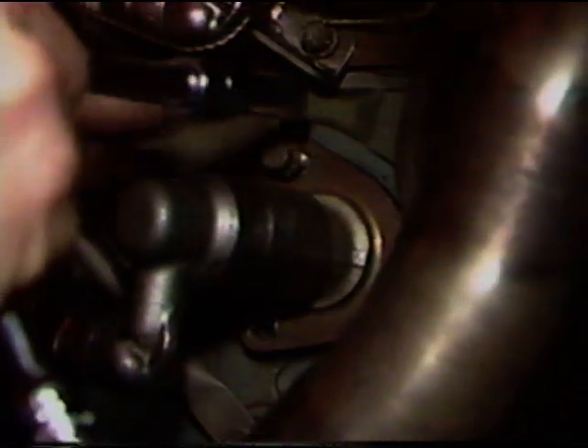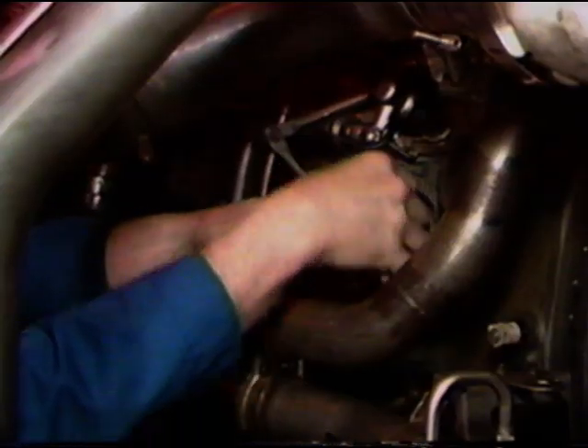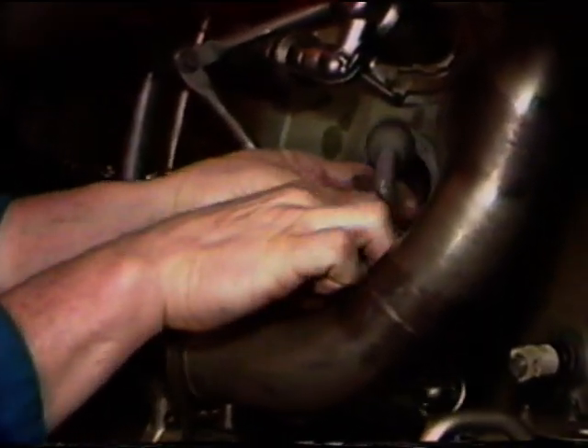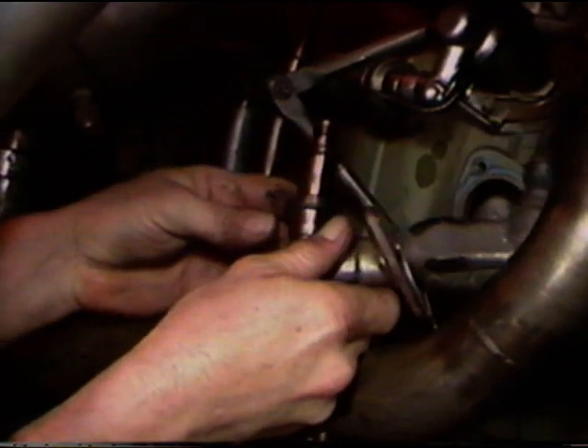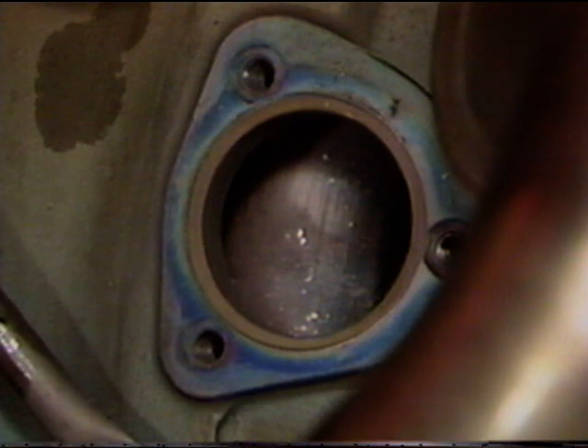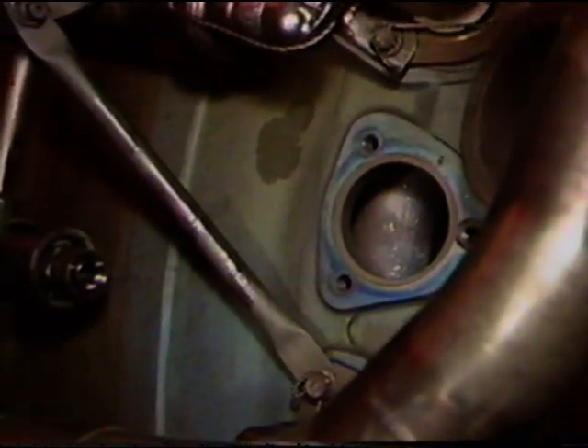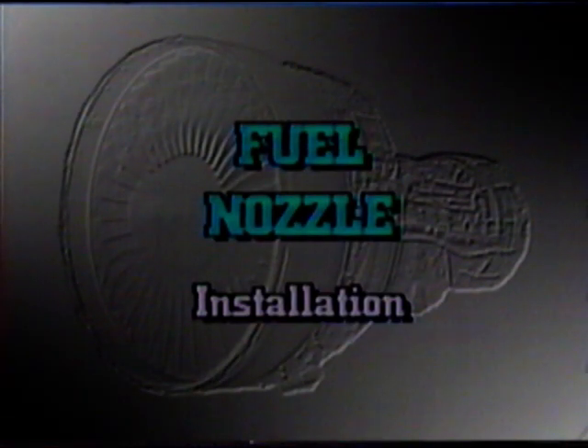After removing the safety wire, remove the 3 bolts that secure the nozzle to the compressor rear frame. Note that some support brackets will need to be removed at some fuel nozzle locations. Make sure to protect the combustor internal casing and mounting pad if it will be open for an extended period of time. Fuel nozzle installation.